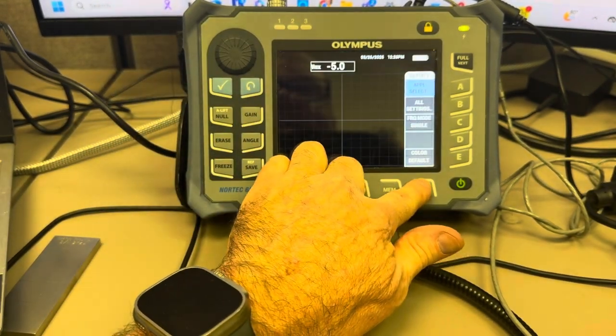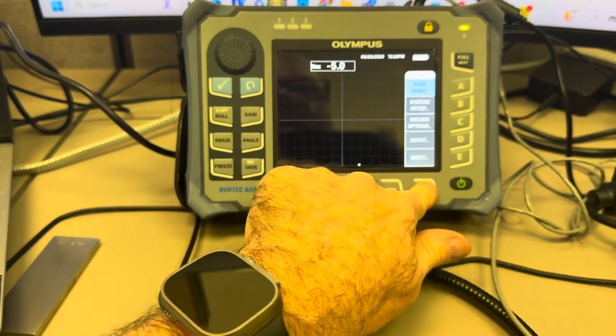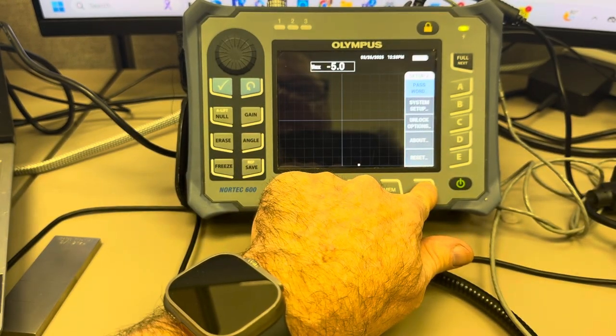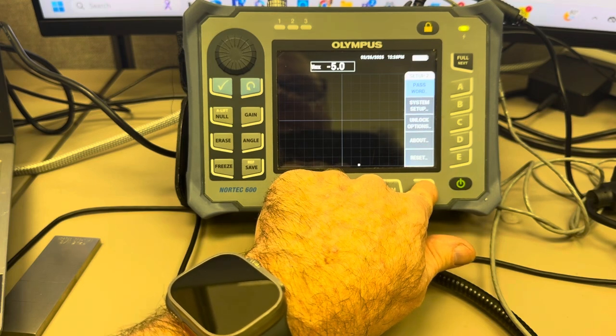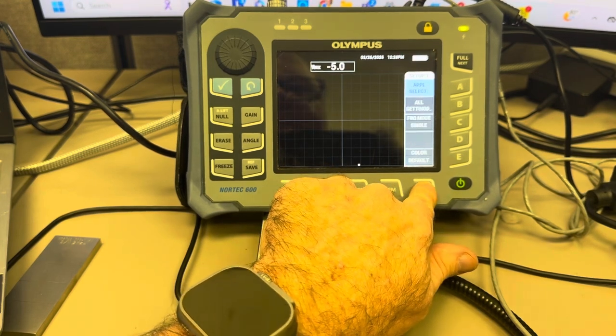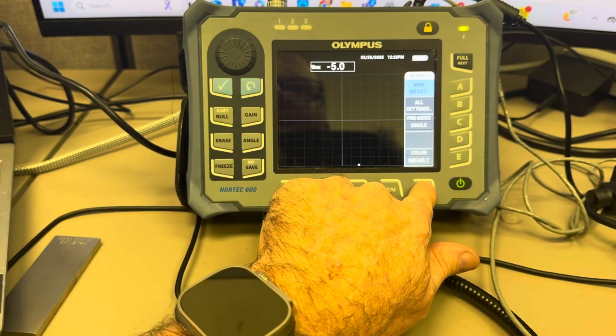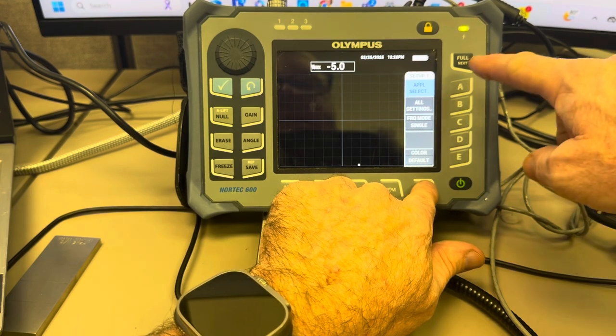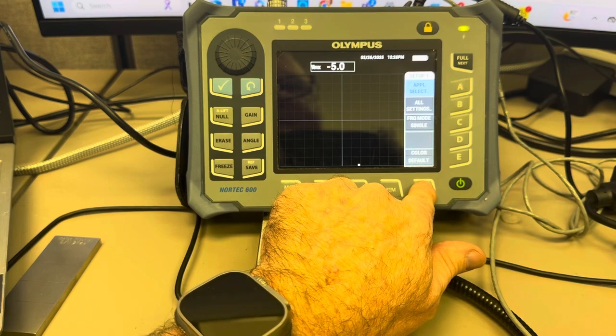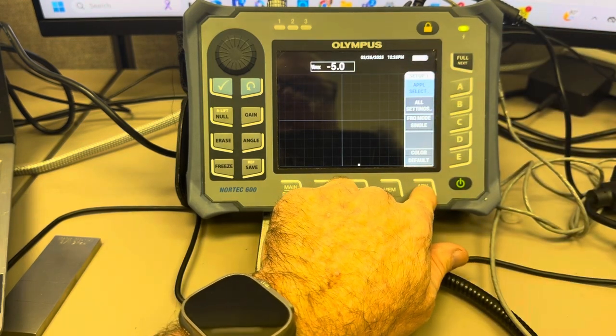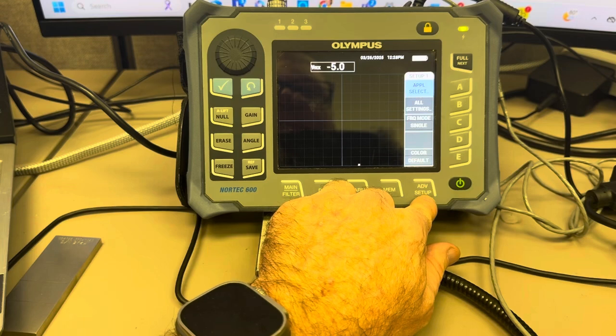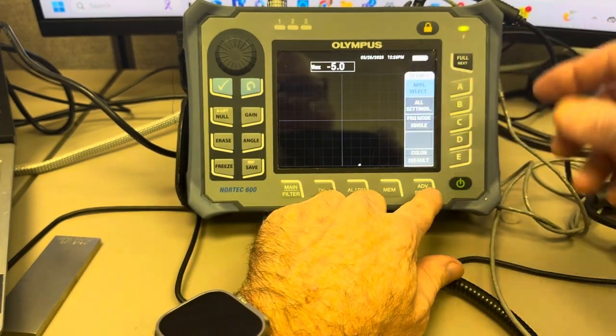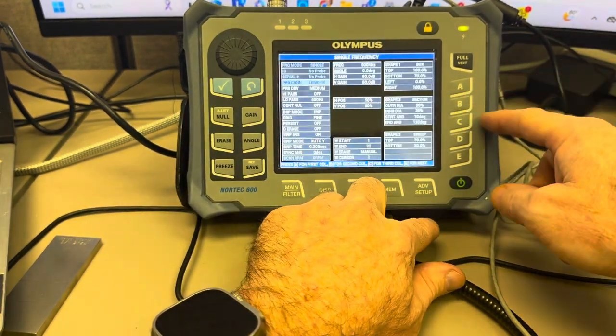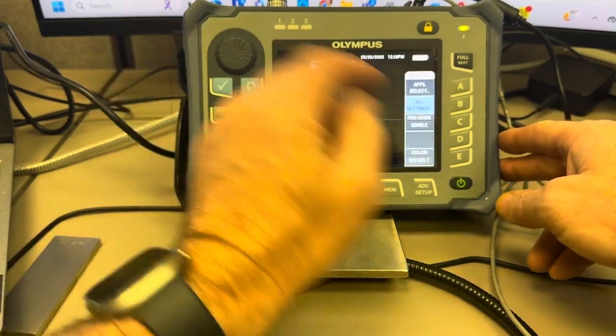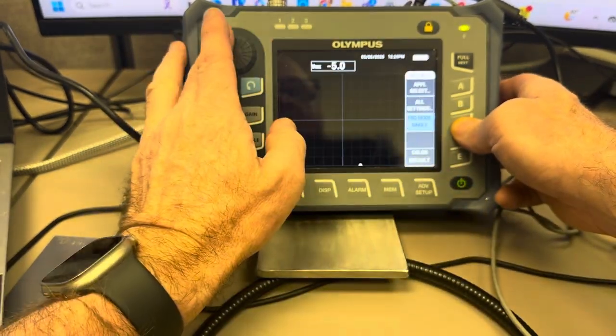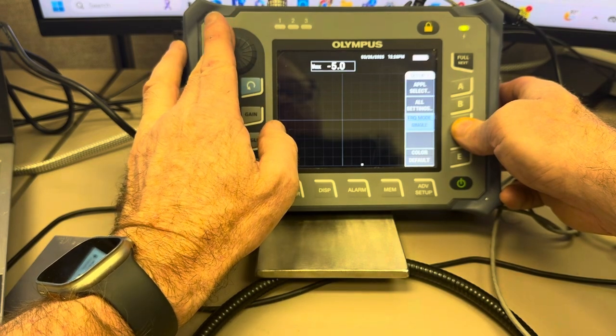Then you've got the advanced setup menu. What's in there? Let's hit it a few times. You can change your password, set up your system. You can lock the tester up. You can reset the tester back to factory. Let's see what else we got in there. Now, A, B, C, D, E, those are all function keys that are tied to whatever menu's up there. So if I click on the advanced menu and go into the setup one set of features, I guess, then I can go into all settings, or I can go back with this key. I can toggle between single and dual frequencies.